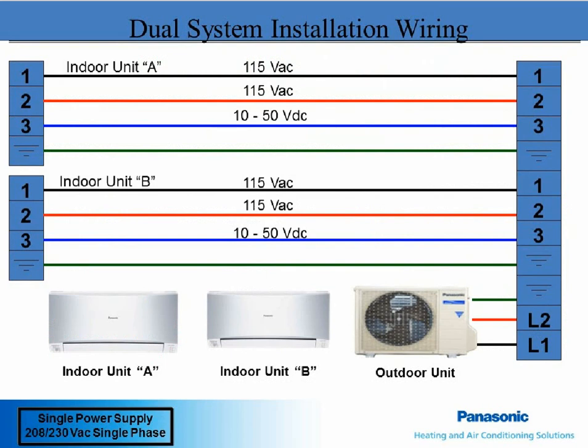With multi-zone systems, you run the same 3 wire with the ground from the outdoor unit to each indoor unit. Again, there is only one power supply circuit run to the condenser, and it also powers each indoor unit.